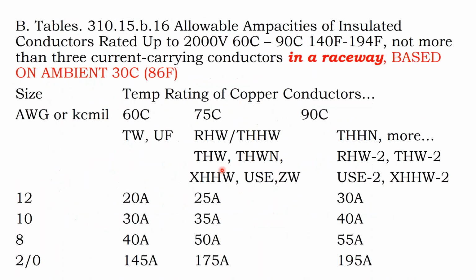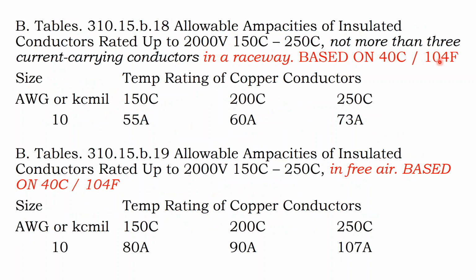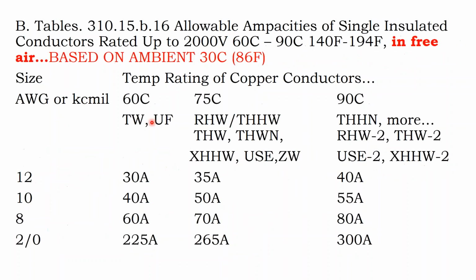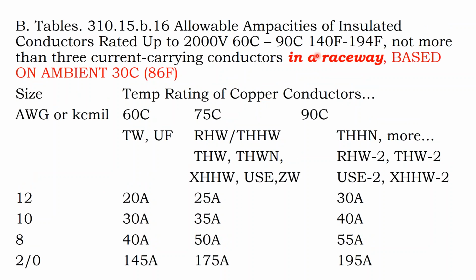because when I look up the differences between, let's say, 86 degrees in a raceway versus 104 degrees in a raceway, we look at number 10, and then we're getting into higher temperature rated conductors, where we're in a raceway at a hotter temperature, and this number 10 needs a 150C rating to carry 55 amps. Whereas before, in a raceway, we see that this 90C rating is not sufficient to carry 55 amps, so we'd have to go up to number 8.